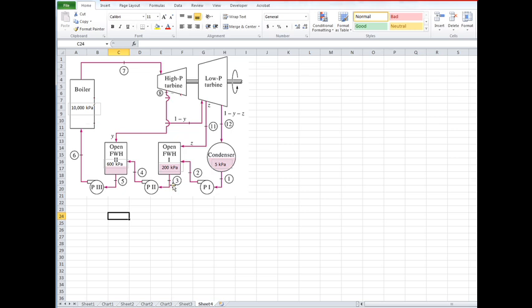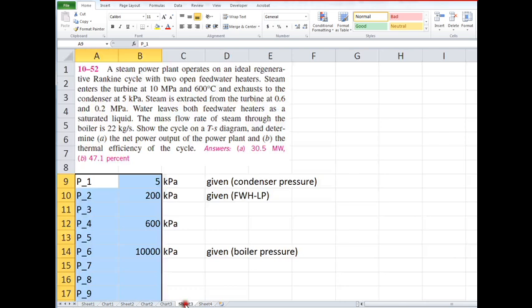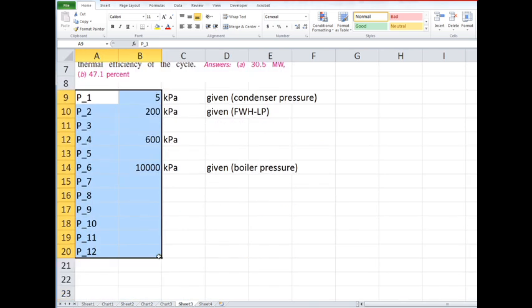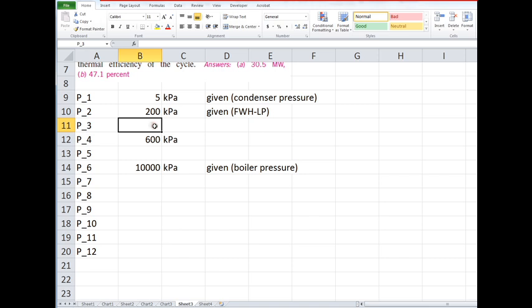Once we find that one, we go to the next feedwater heater and write the equations for that one. That one's going to involve the fraction y, and we will need to have found z first. So always start with the feedwater heater closest to the boiler—in this case, feedwater heater two.